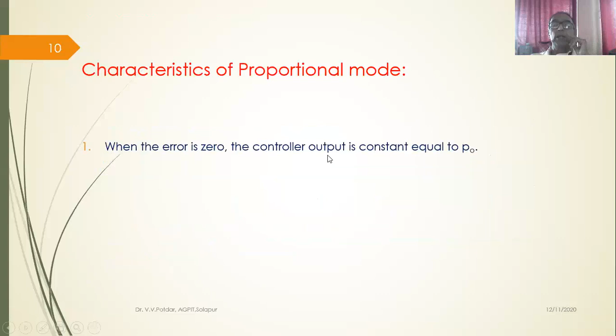Now the characteristics we should know. When the error is 0, the controller output is constant, equal to P0. If the error occurs, then for every 1% error, a correction of Kp percent is achieved. If the error is positive, Kp percent correction gets added to P0. If error is negative, Kp percent correction gets subtracted from P0. This will be very clear from the equation. The band of error exists for which output of the controller is between 0 to 100% without saturation.